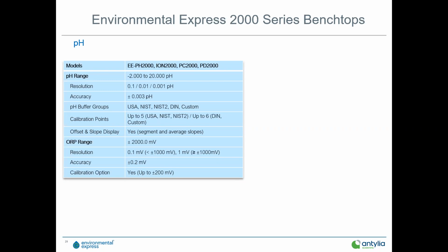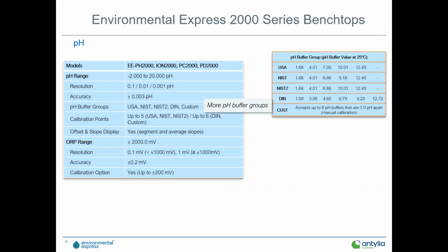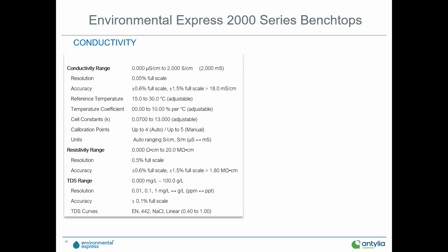Expanded buffer groups in this one: USA, NIST, NIST2, DIN, as well as custom. Up to 5 calibration points on the USA, NIST, and NIST2, up to 6 on the DIN and custom. Offset and slope display, full range for the ORP. And then this gives you some insight to the different buffer groups. Pretty common. We carry all of these, USA, NIST1, NIST2, but not all the DIN. So more buffer groups, shows the segment and slopes, allows for direct ORP calibration.